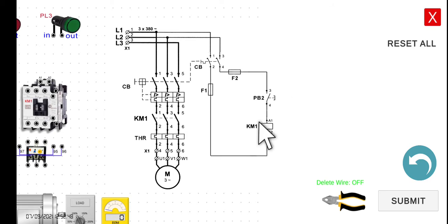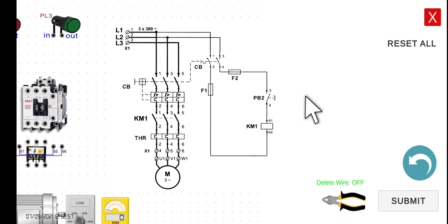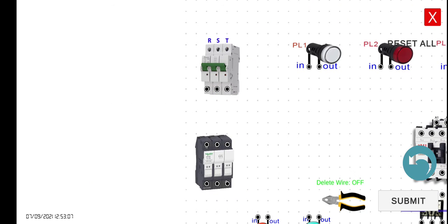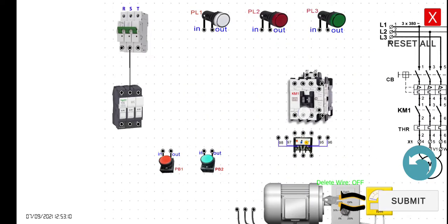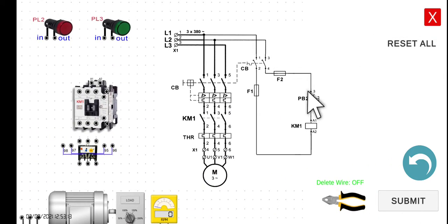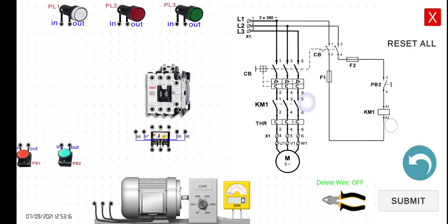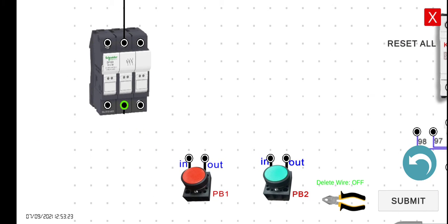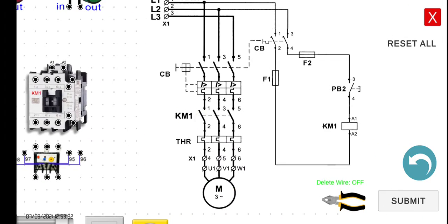So let's try to wire it first. This is the control circuit, and this one is the power circuit. Let's try to wire first the control circuit. We have to wire from line 2 to fuse 2 — the circuit breaker to fuse 2. After fuse 2, we have to connect this one to the input of our push button here, push button number 2.